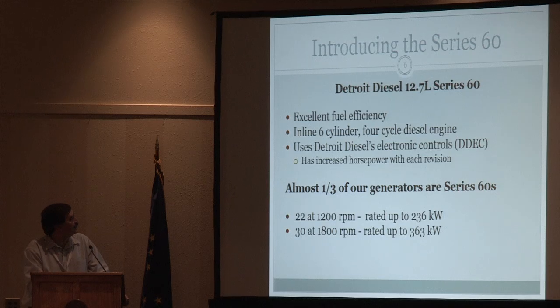At AVEC, we have over 50 of these Series 60 units running out in our plants, scattered all over the place. They're rated up to 363 kW with excellent fuel efficiency, and that's why we use them - fuel is king out in rural Alaska. They're inline 6-cylinder, 4-cycle diesel engines using Detroit Diesel electronic controls, the DDEC. They got up to DDEC 4, increasing in horsepower with each revision, so you have different horsepower units out there. We have 1,200 RPM units going up to 236 kW, and 30 units at 1,800 RPM up to 363 kW. So in our small communities, they're a good engine for the 300 kW range.